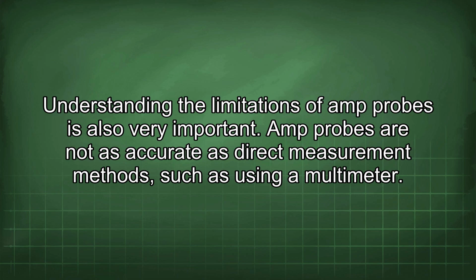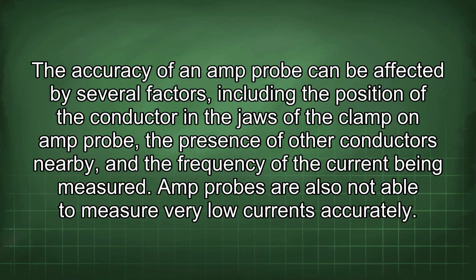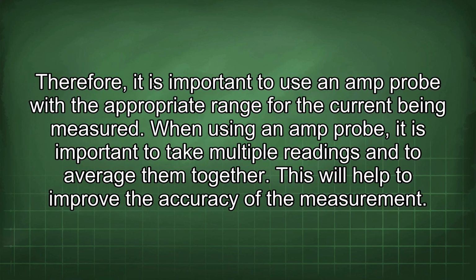Understanding the limitations of amp probes is also very important. Amp probes are not as accurate as direct measurement methods, such as using a multimeter. The accuracy of an amp probe can be affected by several factors, including the position of the conductor in the jaws of the clamp-on amp probe, the presence of other conductors nearby, and the frequency of the current being measured. Amp probes are also not able to measure very low currents accurately. Therefore, it is important to use an amp probe with the appropriate range for the current being measured.